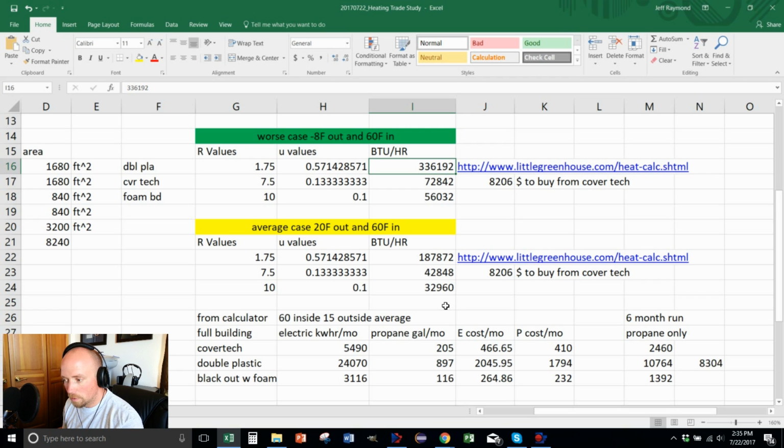So, actually, I did do that calculation. I've got it right here in front of me, on a piece of paper. The propane would be $2,800 a month for the full BTU if we only use the double poly. And I also looked at diesel.